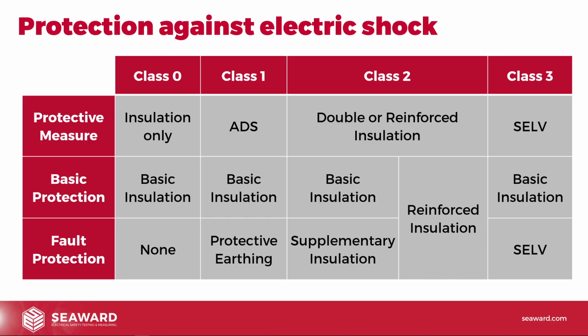And then the final one, Class 3, that we talked about, that utilises the protective measure of SELV, separated extra low voltage. The basic protection, again, generally is still basic insulation, but the fault protection is provided by SELV. So in the case of SELV, we're separated from earth, so we can't get any faults to earth at all. There's just no circuit there, so it's impossible to get electric shock between earth and any of the live conductors. And if we do touch the live conductors directly, between the 2 live conductors, it's going to be an ELV, an extra low voltage, so it's going to be a safe level of voltage anyway. So that's what makes Class 3 or SELV systems super safe. And they're the ones, as I say, we use in environments where there's increased risk.